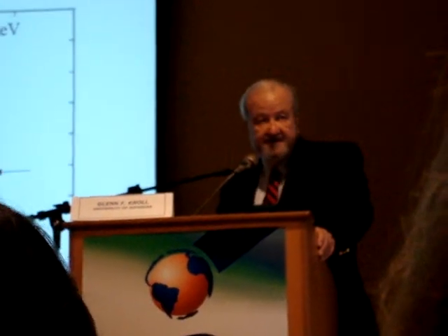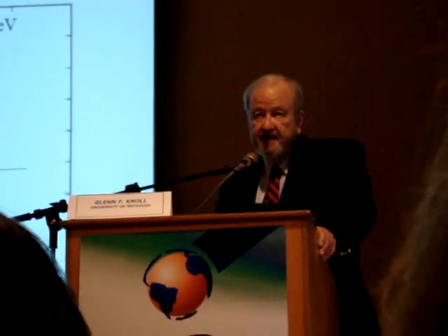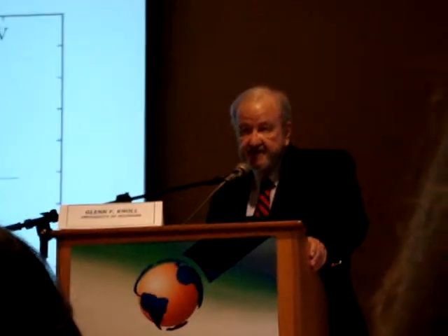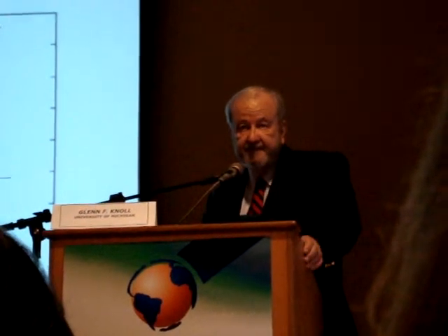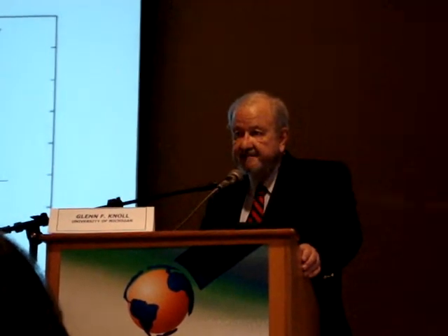Germanium at cesium energy would have something like about a 0.2% energy resolution. So you'd still be about a factor 2 or more away from germanium, but this is room temperature and not cooled. So it would have some strong attraction for portable instruments, for example, areas where the liquid nitrogen is a real hindrance.